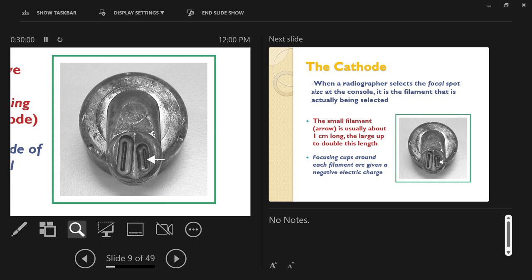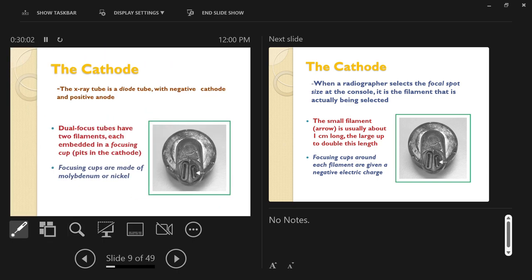Engineers have made it so we can't easily damage the equipment — we want x-ray tubes to last a long time. The filament wire needs to be very strong and tough, so it's made of tungsten. Most of you probably know tungsten from tungsten wedding bands: they're a strong, dense metal with a high atomic number and a very high melting point.